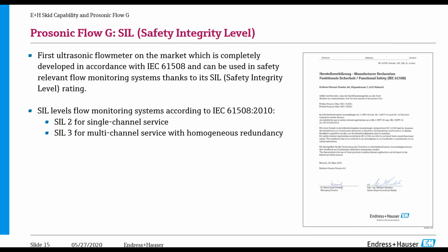This is the first flow meter on the market with SIL. SIL is for safety critical applications and stands for safety integrity level, and we have different ratings on there. We have SIL 2 and 3. This is a standard called IEC 61508. And so right now we're the only one on the market with a SIL approved device.